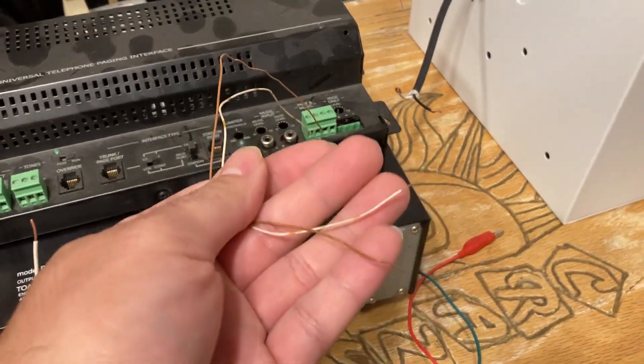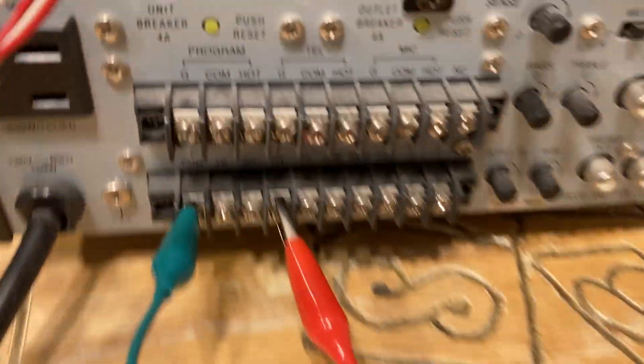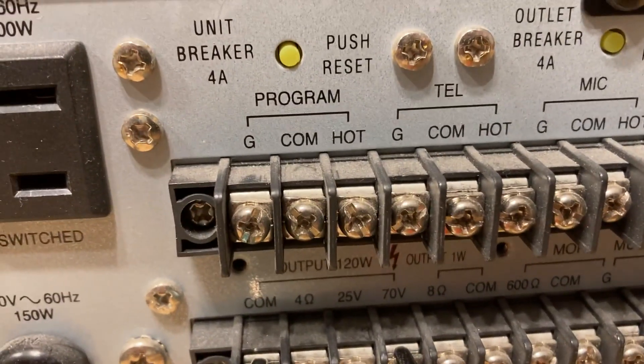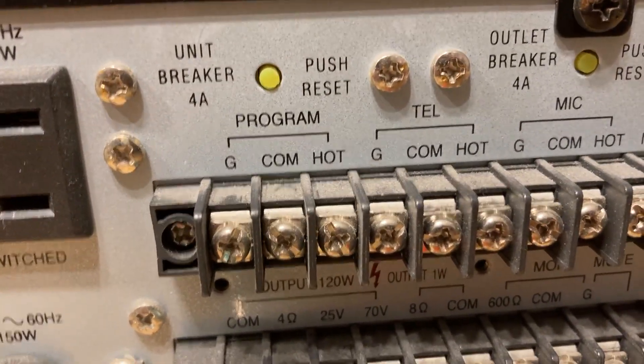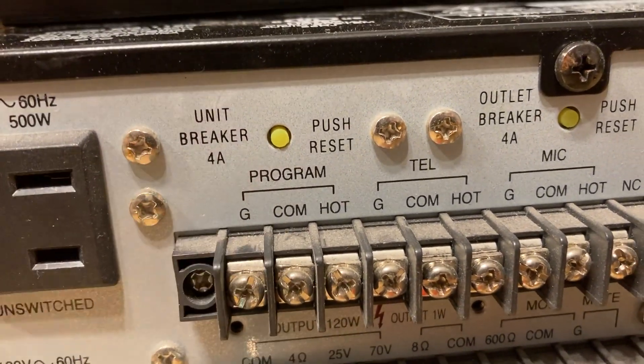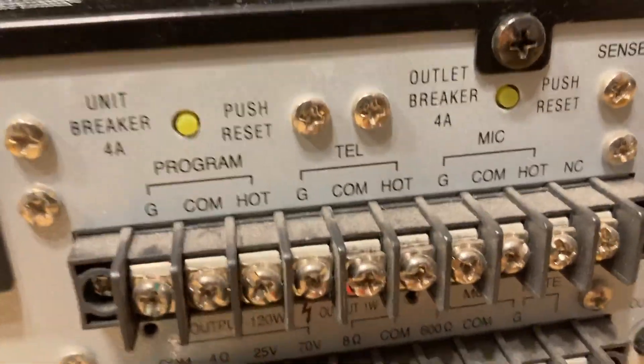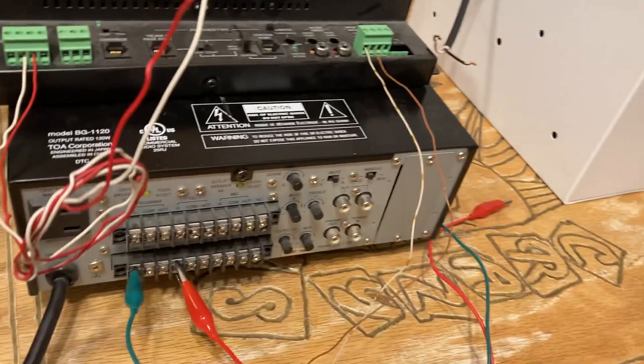I noticed the same viewer likes to land his page wires — the tip and ring — onto the program terminals. There's nothing wrong with that, but if you're going to use the mute function it will mute your program and you won't get any page. Use the TEL terminals — there's a reason those TEL terminals are there.